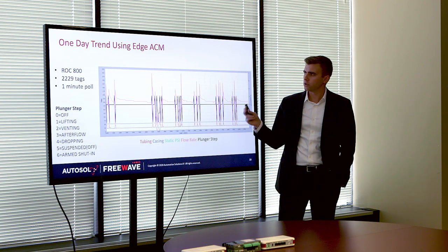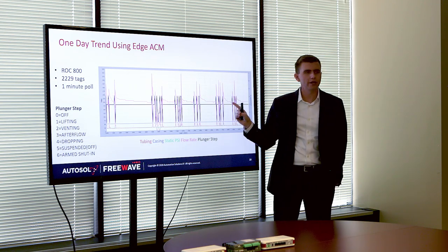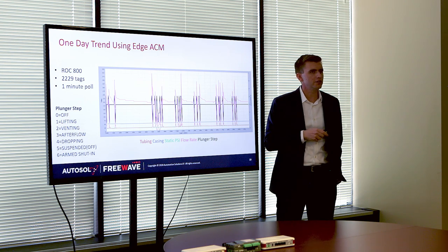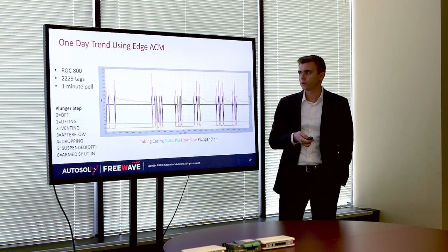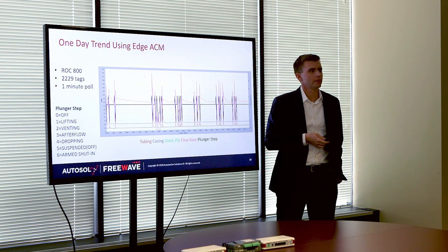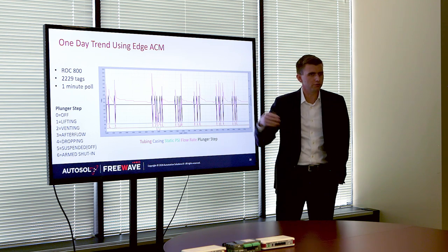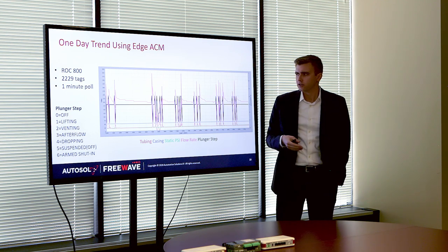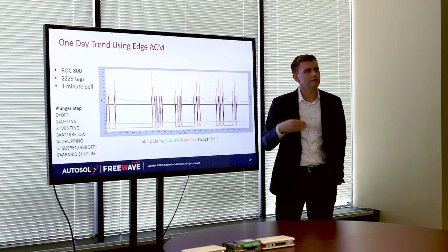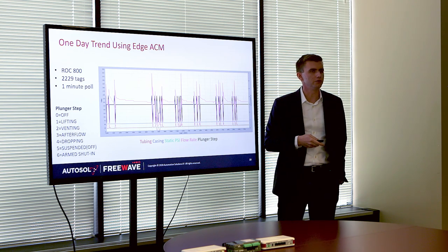This is what one day looks like with Edge ACM — actually information they were able to make an optimization decision on in one-fourteenth of the time it used to take. They told us it used to take 7 to 14 days after making a tweak to their plunger lift to see if the optimization took effect. We took it from 14 days to less than one day because we can get them higher resolution data.